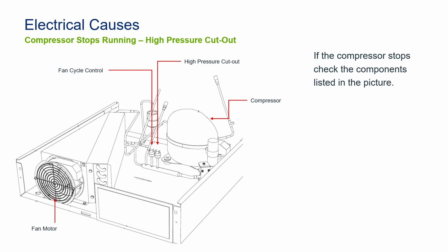Close the contacts and run the fan motor. Continue to run the fan motor until we've rejected enough heat that our pressure comes down to the cutout point of that switch. Open the contacts and stop running the fan. Build up more heat again, close and run, and continue on a loop as we go. But let's say that didn't happen.